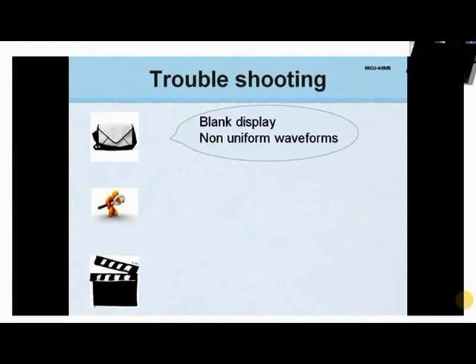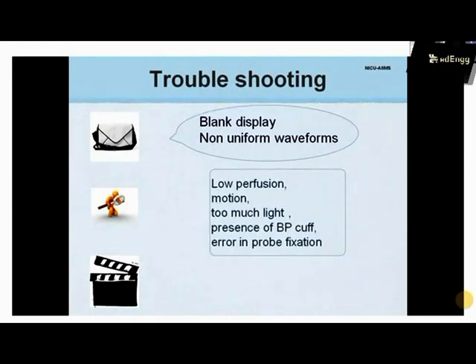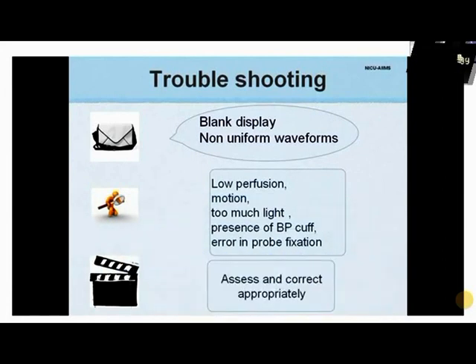In case of a blank display or non-uniform waveforms, the causes could be many: low perfusion, motion, too much light, presence of a BP cuff on the arm, or an error in probe fixation. The actual cause should be actively searched for and corrected accordingly.